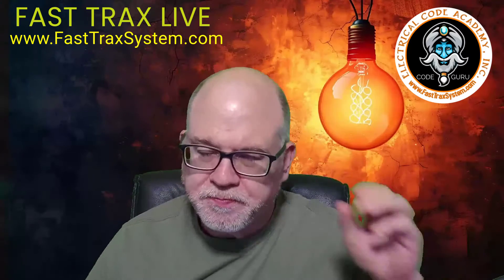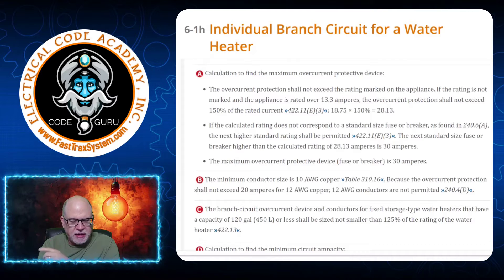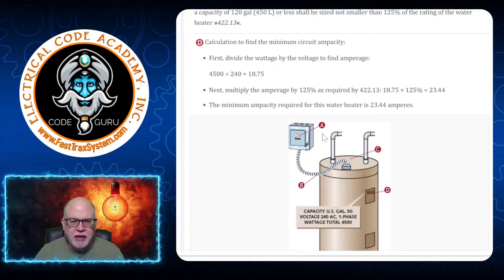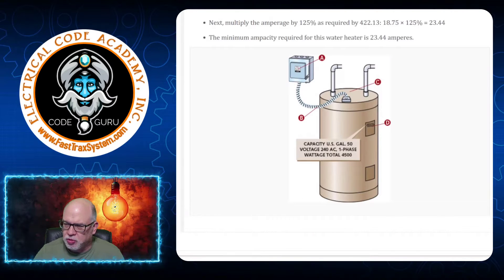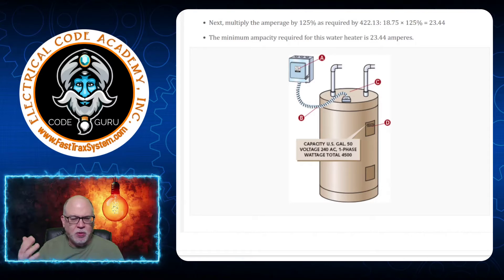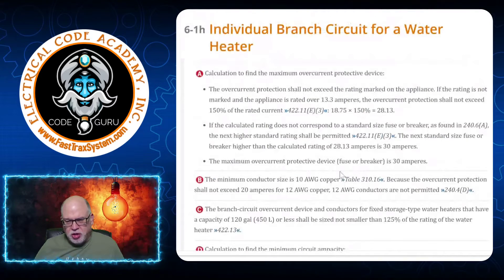So let's go to the lesson. In our Fast Tracks program, this is what you'll learn in Unit 6, section 1H. We're talking about an individual branch circuit for a water heater. Here's our water heater, there's our disconnect — we'll assume the water heater is not within sight of the panel. This is a 50-gallon, 240-volt AC single-phase unit with a total wattage of 4,500 watts — very typical for a water heater today.